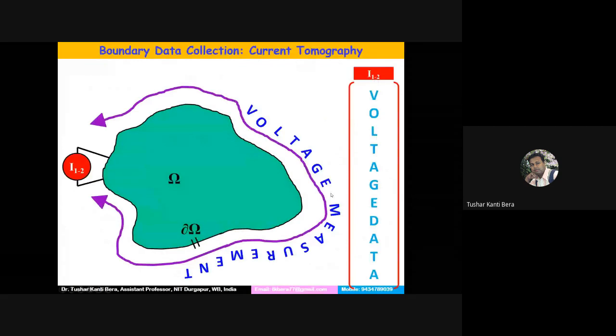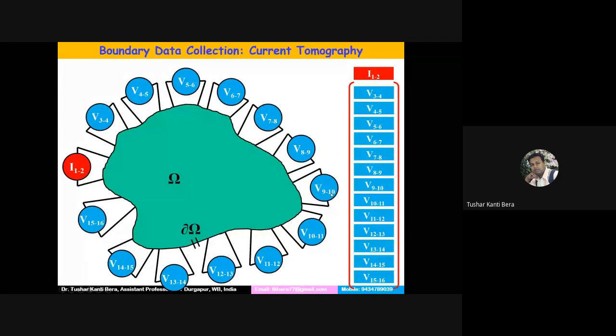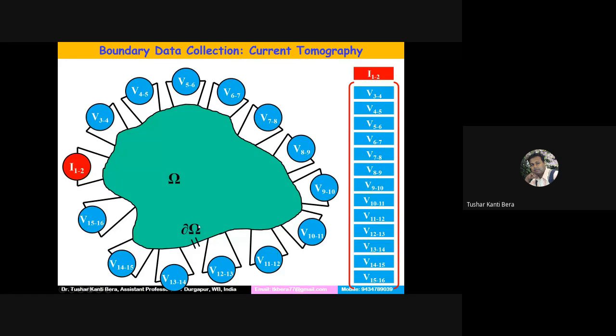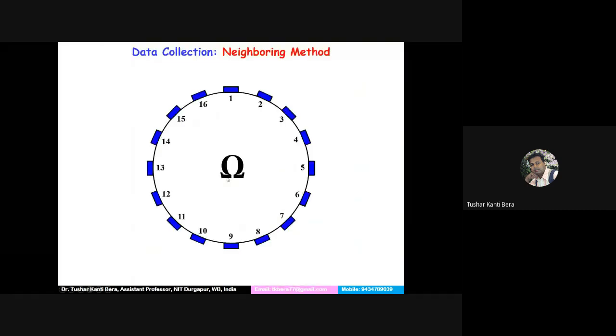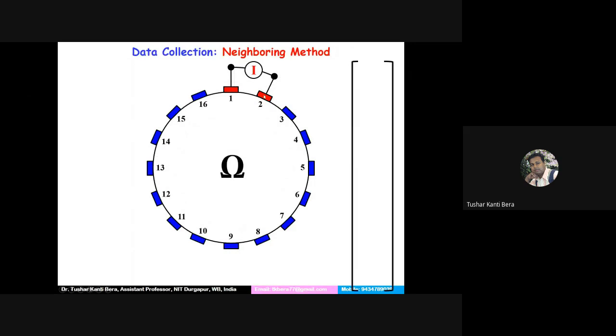There is the current injection technique, the applied current technique, or the applied voltage technique. When the current is applied and voltage is measured, it is the applied current technique. When the voltage is applied and current is measured, that is called the applied voltage technique. But in any case, we have to measure data over the 360-degree rotation, meaning the total boundary will be covered, changing with the position. So this is the first projection, electrodes 1 and 2. After that, the voltage measurement will start from 3 and 4 and stop at 15 and 16. So one voltage data matrix will be obtained.